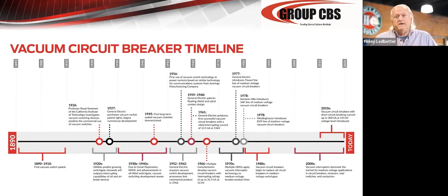And then the air breaker was a combination of the two. It did have some modern materials in it, but it started with organic insulation and big arc chutes and a lot of asbestos and materials that we didn't want in our plants today. And the vacuum breaker solved most of those problems with plastics and epoxies, fast contact speeds, fast opening speeds, very reliable equipment. After they got through the first few rounds of design changes, the vacuum circuit breaker has been very reliable. And if you look today at them that are in service 50 years, you got to say, hey, you've got your money's worth out of this equipment.